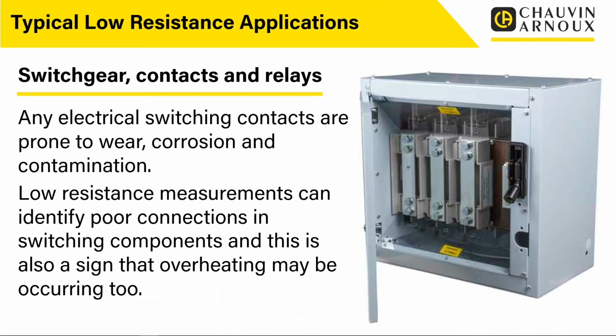By reading across those contacts, we can see that potentially any of these issues are present. So low resistance measurements can identify poor connections in switching components, and this is also a sign that overheating may be occurring too. And as we talked about with the busbars, where you do get poor connections, that's when you're going to start to get heating, and that's when you're going to start to get problems, fires, all sorts of things in there. So by checking our contacts, by making sure these things are set up correctly in the first place, and then monitoring them over time, we can preempt any failures before it gets too serious.